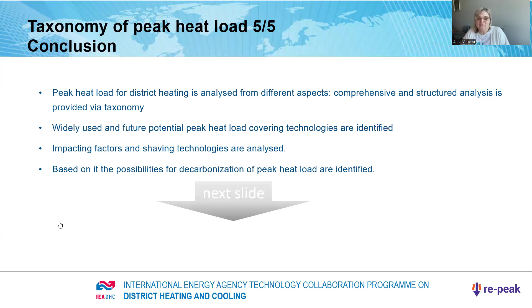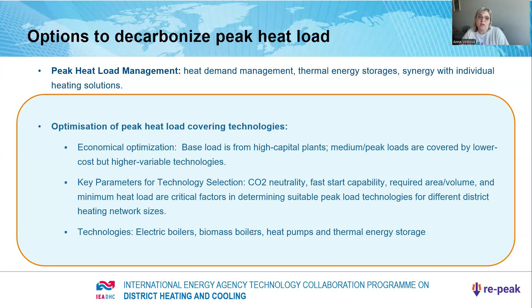But the focus of our research project was on peak heat load covering technologies. It is very important to optimize these covering technologies, both from an economic point of view and by evaluating key parameters for selection, like CO2 neutrality, fast start capability, required size, minimum heat load, and other critical factors. The main technologies analyzed, which you will see in this analysis, are electric boilers, biomass boilers, heat pumps, and in some cases thermal energy storage.